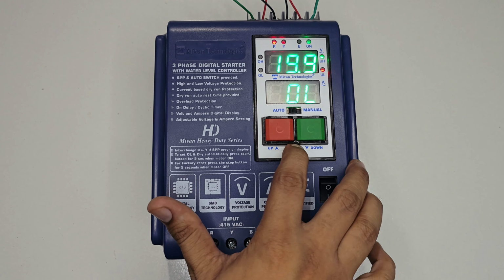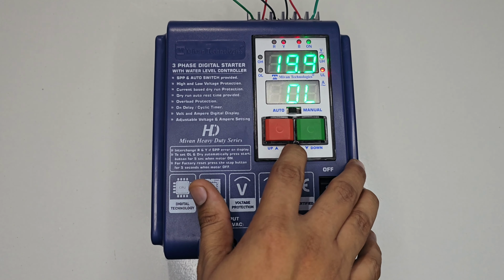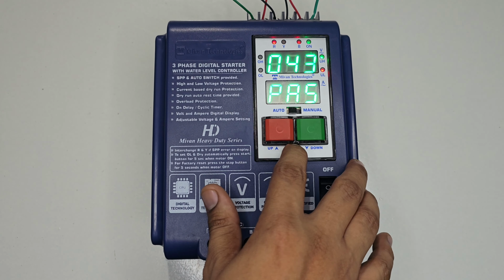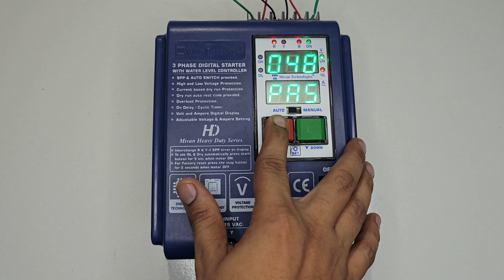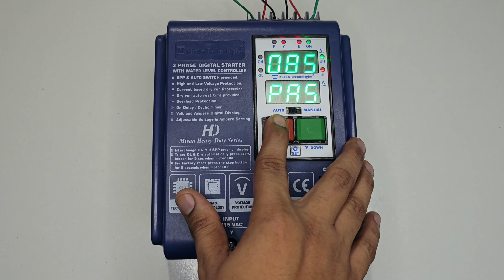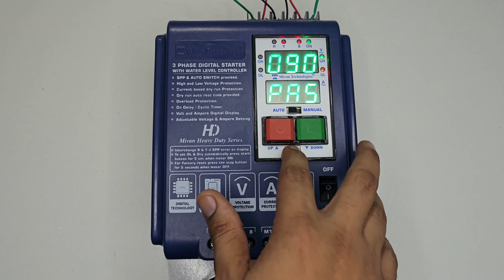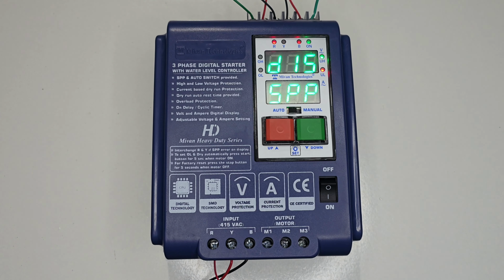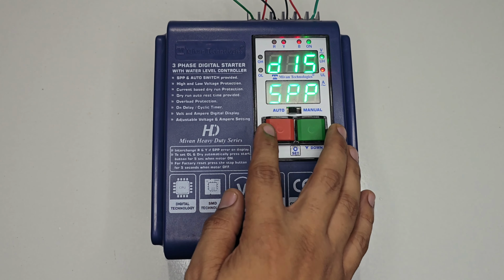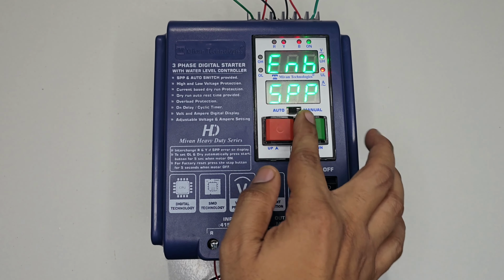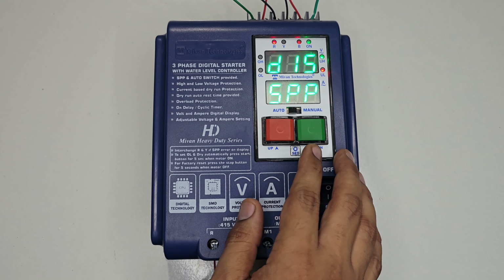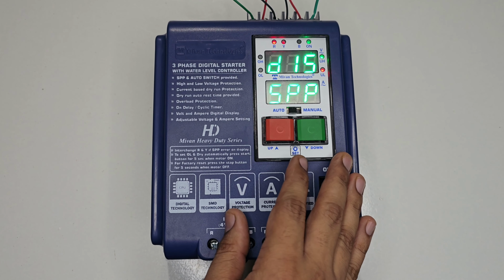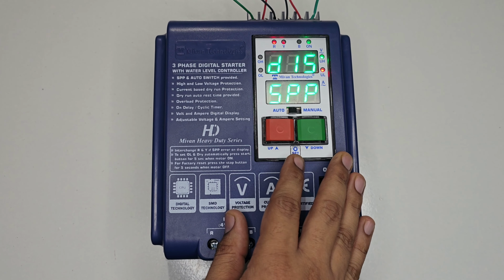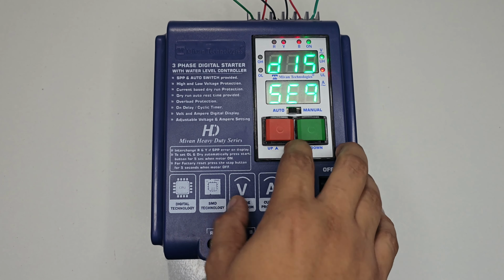Press the set button for 5 seconds. Go to password 90. Press the set button. Here you can disable the SPP function. If you have disabled this SPP function, then phase loss protection will be bypassed. Press the set button.